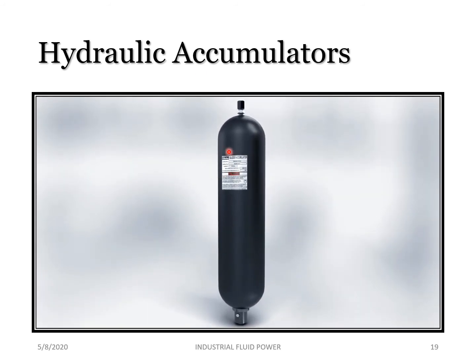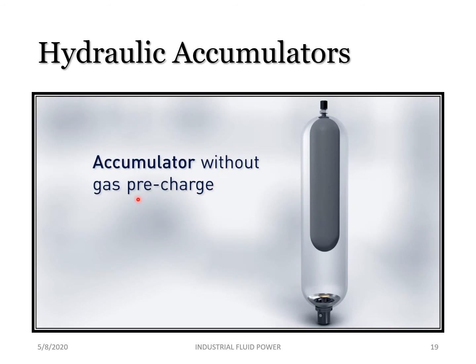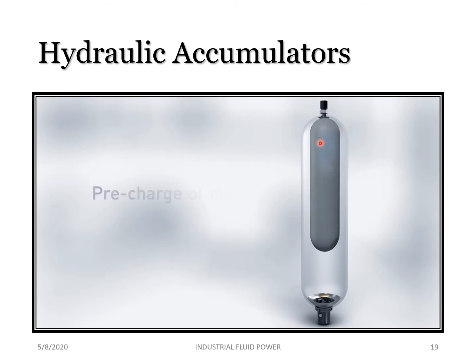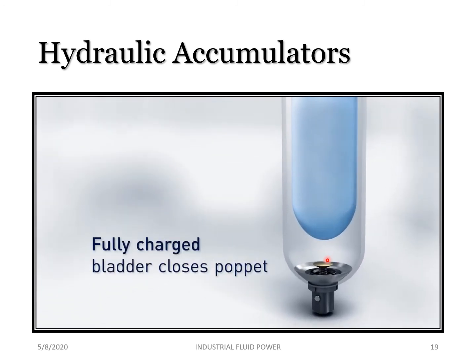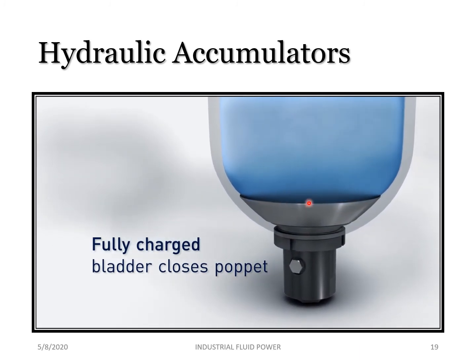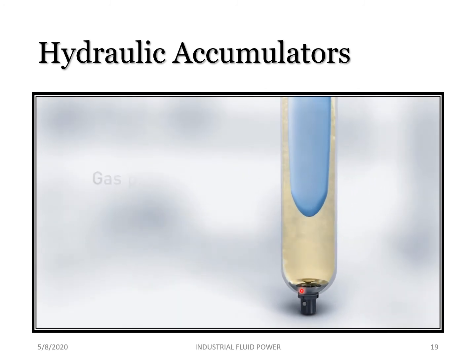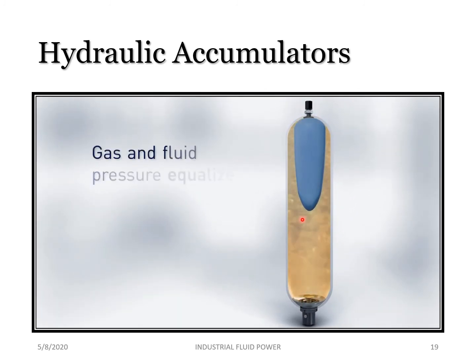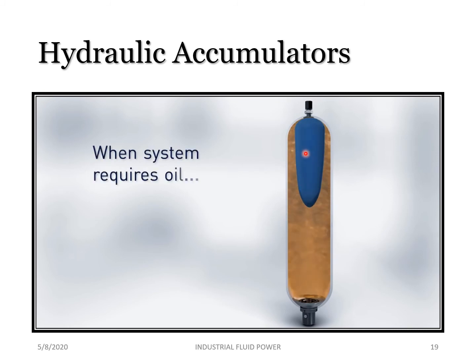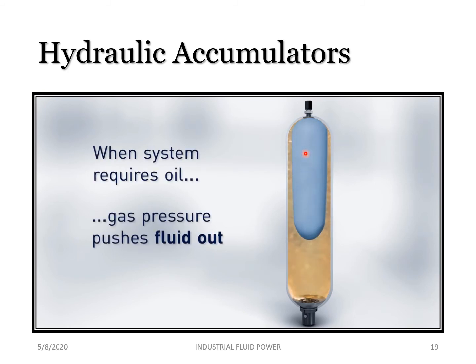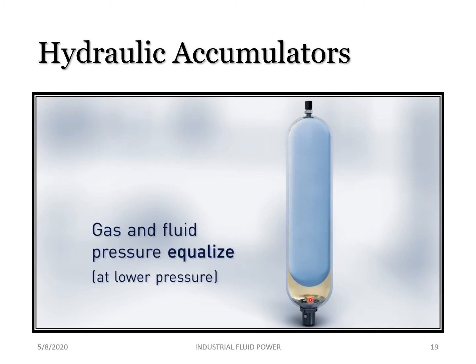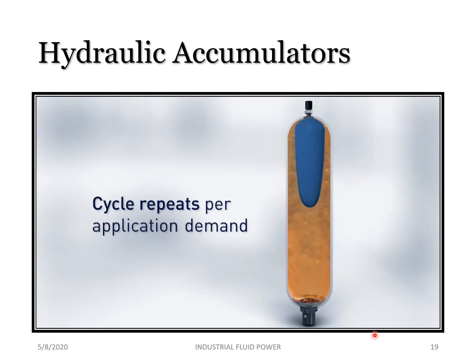This is how the gas pressurized accumulator works. Without gas pre-charge it looks empty. The bladder is now being pre-charged with gas — the bladder expands and fills until it is fully charged. When high pressurized fluid flows in, it compresses and squeezes the bladder. When the system requires oil, the gas pressure pushes the stored fluid out of the accumulator. The bladder is compressed during charging and expanded during discharge.